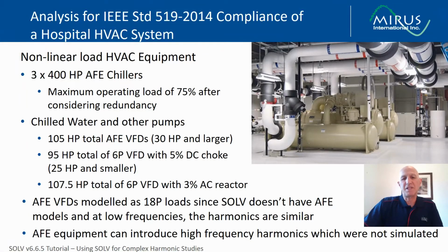The AFE VFDs were modeled as 18-pulse loads, since SOLV doesn't have AFE models. And at low frequencies, the harmonics are similar. But AFE equipment can introduce high-frequency harmonics, which were not simulated.